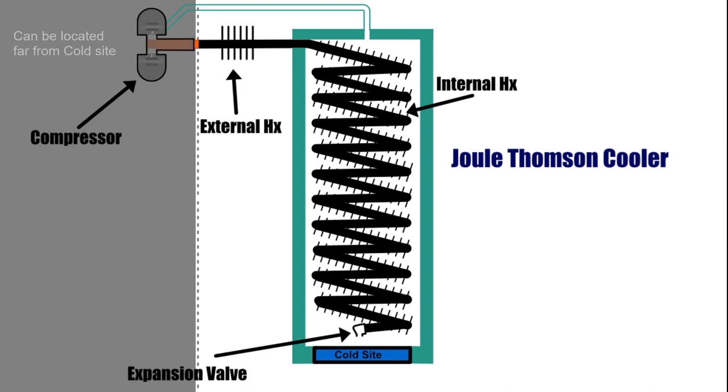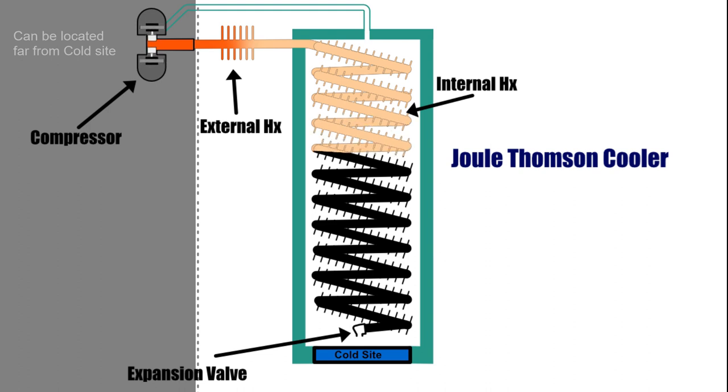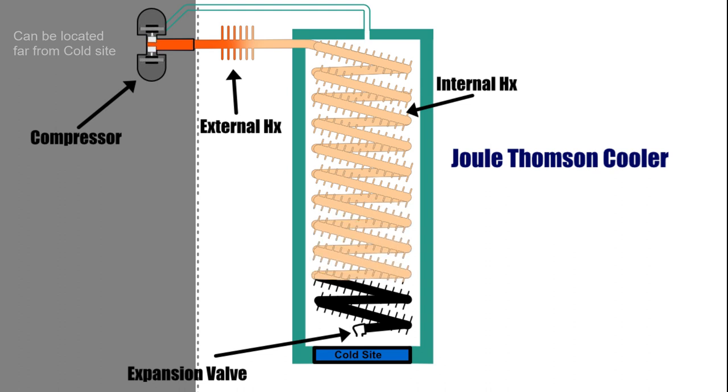High pressure gas as it leaves the compressor is partially cooled by an external heat exchanger before it enters the internal heat exchanger. After the high pressure and now partially cooled gas passes the internal heat exchanger, it will then flow through an expansion valve and into a low pressure chamber.